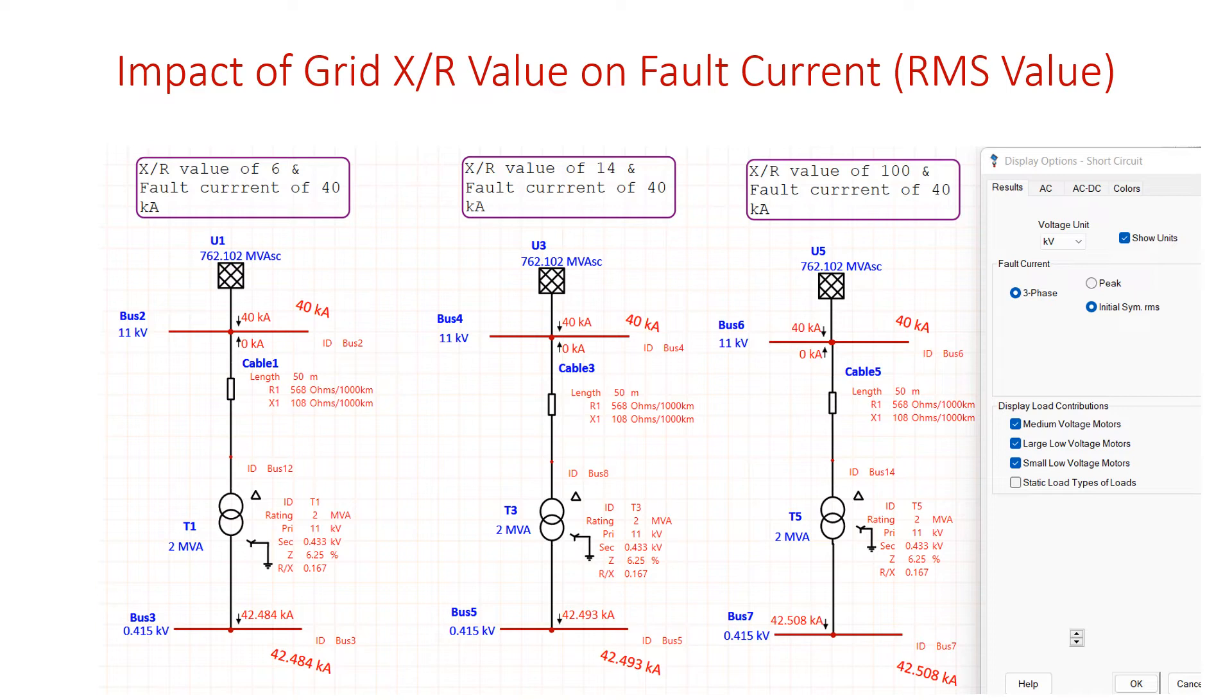If I change the X by R value as 14 or 100, it doesn't matter. The fault current on bus number 4 and bus number 6 is 40 kilo amps and bus number 5, bus number 7 is almost 42 kilo amps. There is no major change observed in initial symmetrical RMS value.